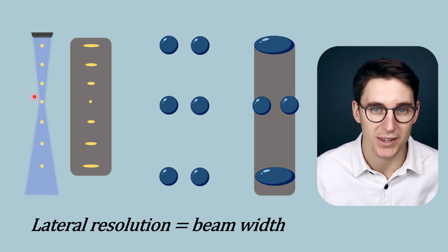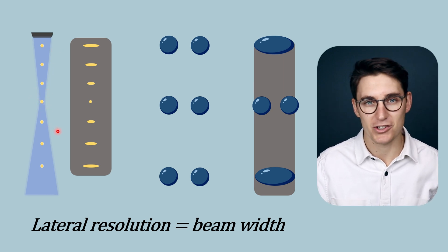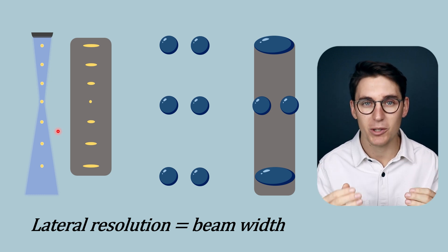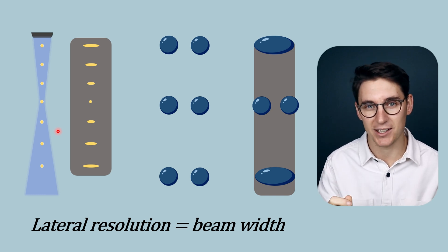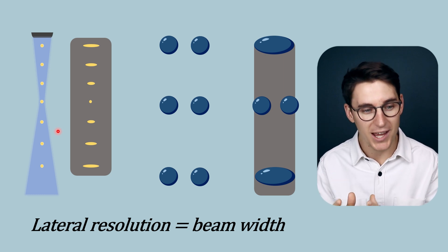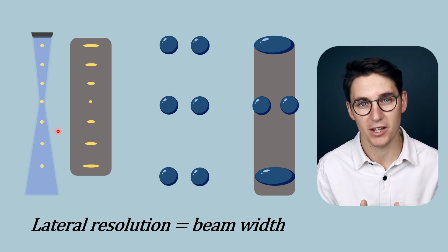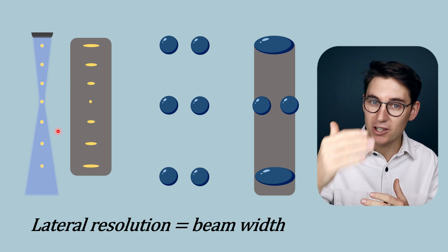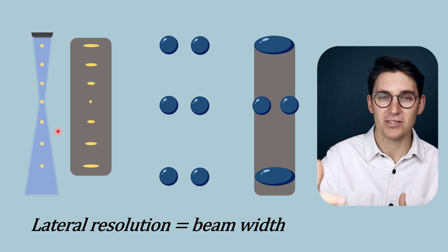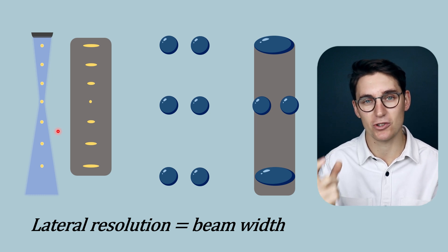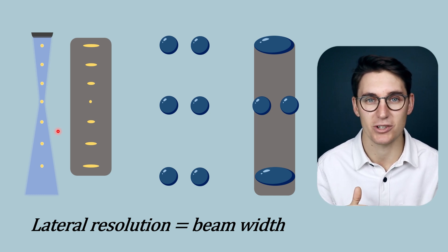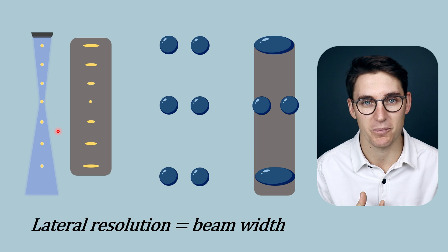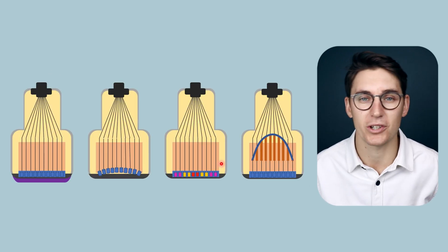The shape of our ultrasound beam is dependent on the diameter of the transducer elements and the frequency of the wave. For a given anatomy, we generally keep both the transducer diameter and frequency fixed. So how do we improve lateral resolution with depth when using a set probe? If we want good lateral resolution at both 5 cm and 15 cm into our image, the answer comes down to beam focusing — we can manipulate the ultrasound beam, and there are four separate ways to focus a beam.